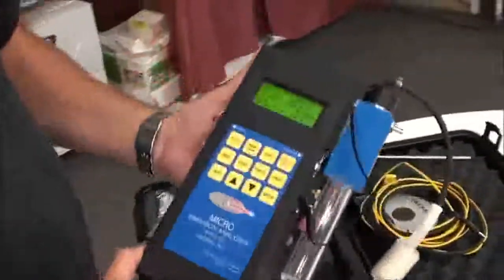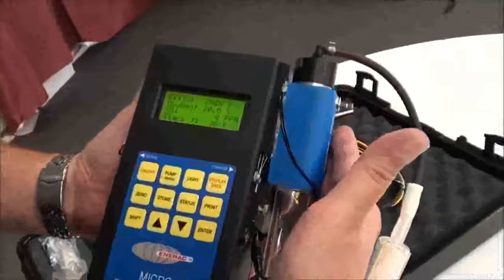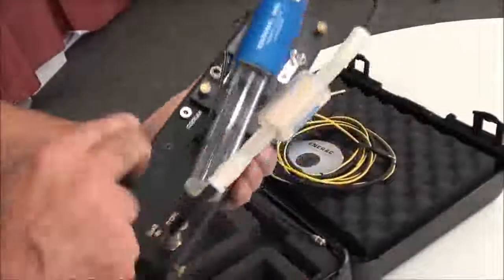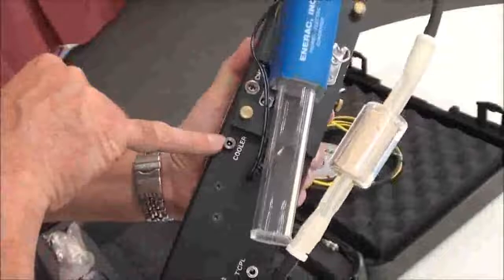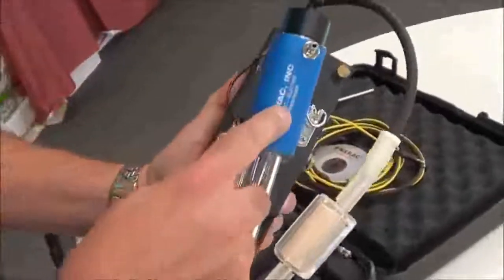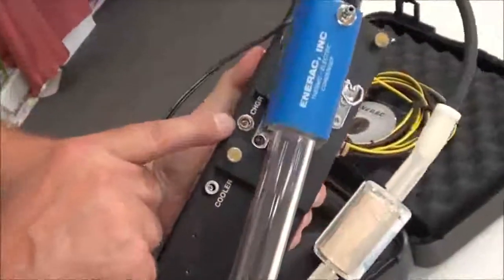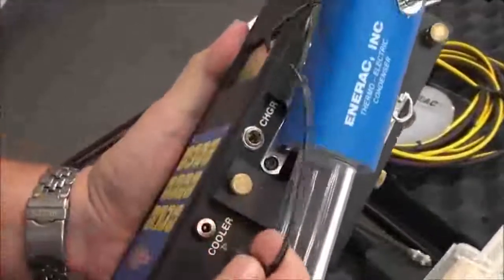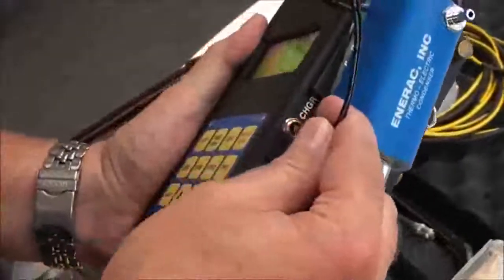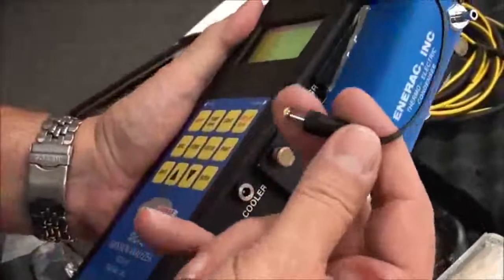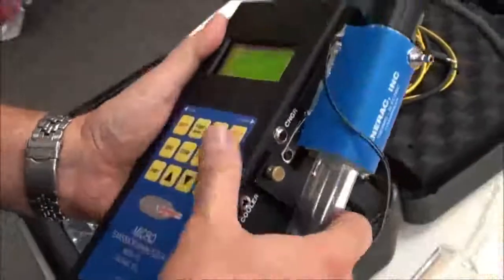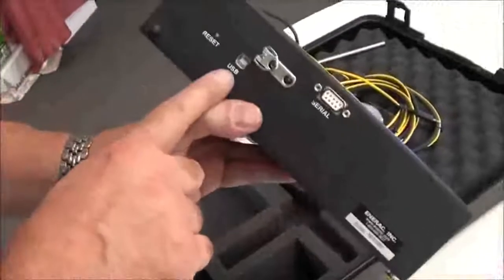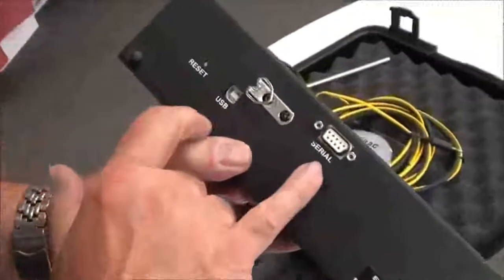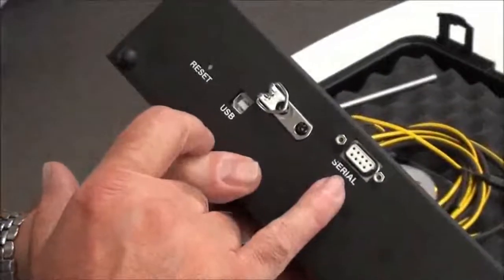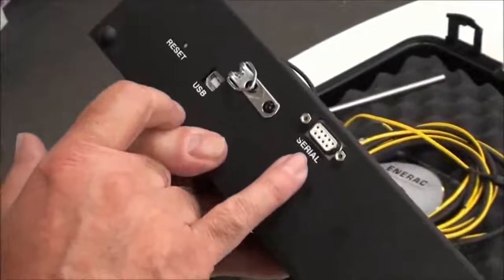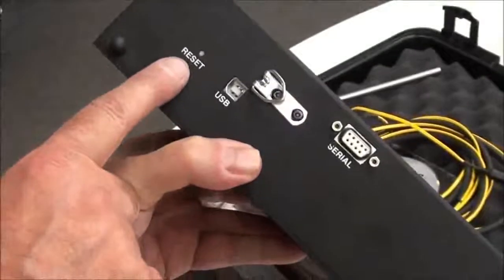Normally, if you purchase a unit with the cooler, it will be mounted on the side. There are 2 plugs on the side. One is for the cooler, because this is a powered device, and the other one is for the charge jack. Just be careful you don't inadvertently plug them into the wrong jack, otherwise you may damage this connector. On the other side, you've got a USB port and a serial port. This is a standard 9-pin serial port you can connect to any computer. And then you have the reset button.